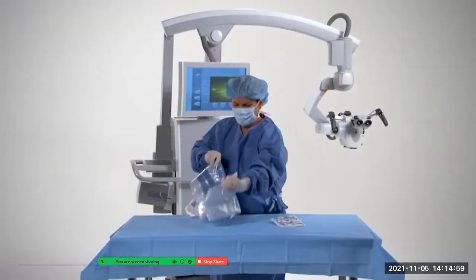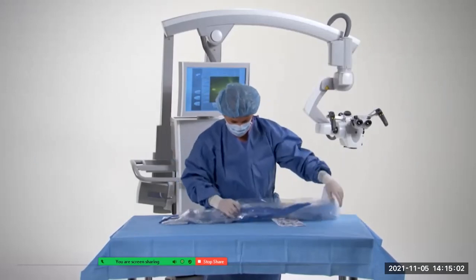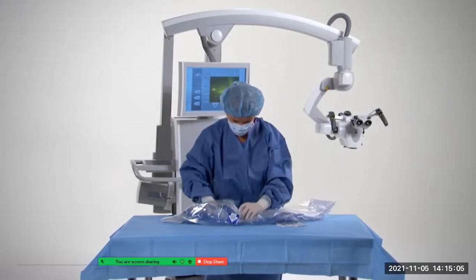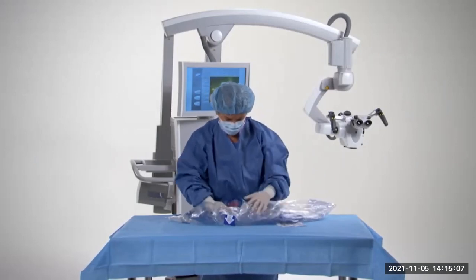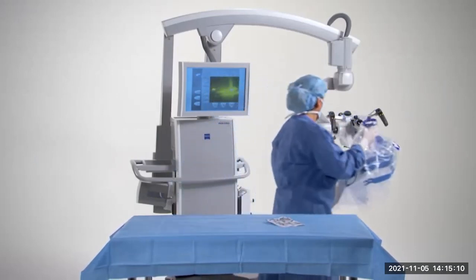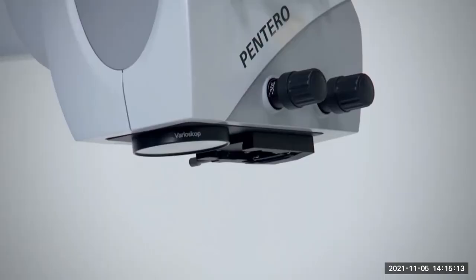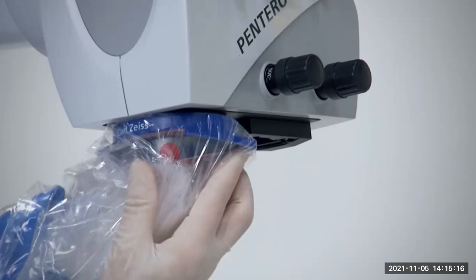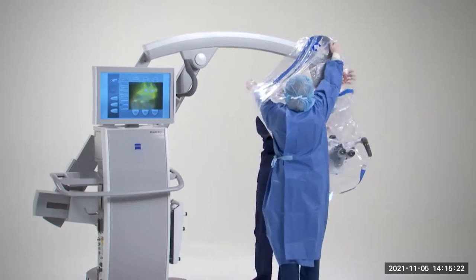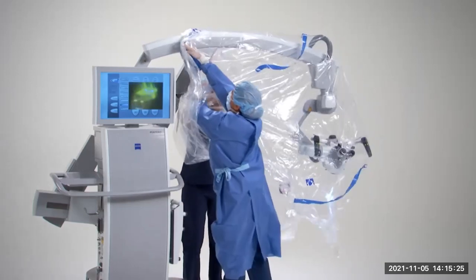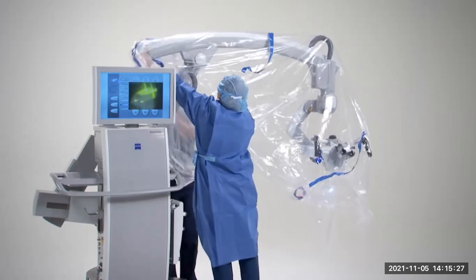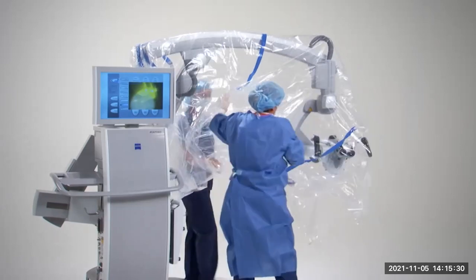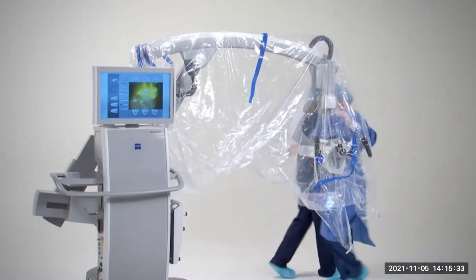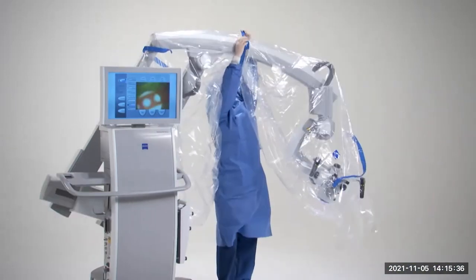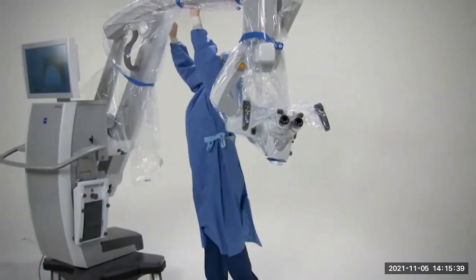To drape the microscope manually, make sure that the drape button on the touchscreen is inactive. After unfolding the drape, insert your hands into the special positions indicated by the stickers on the drape. The OPMI drape has a special lens fitting for the objective. Place the fitting over the objective, and then move the drape over the head of the microscope and hand grips. Make sure that there is slack in the drape to allow for swivel, tilt, and rotation of the microscope, especially around the hand grips. Pull the drape over the rest of the arm. Using one of the straps, make the drape airtight at the farthest position.